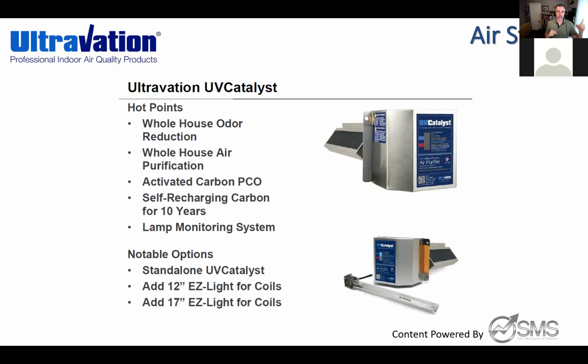Ozone is created off of UV bulbs and off of the PCO process, but ozone off of UV bulbs is temporary. Most standard UVC wavelength bulbs have a 100-hour burn-in period—most people don't talk about this, doesn't matter who makes it. The initial 100 hours, once you light the bulb, it's breaking itself in and heating up, so it gives off a little off-gassing of ozone. But after the first 100 hours that dissipates and it's done—the bulb is broken in and doing its thing. So if people have that rare concern about ozone, keep that in mind. The advantage of our T3 bulb is that because it's encapsulated in a quartz sleeve, that off-gassing can never happen—there's no ozone coming off the T3 bulb. So we have that advantage.